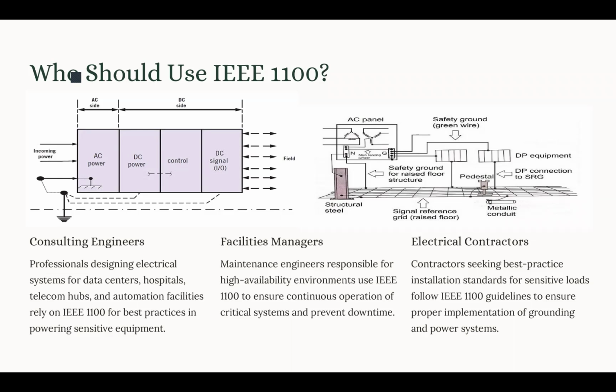Now they have to make sure they have proper grounding and bonding. So basically, bond isolated ground bars directly to the SRGs for sensitive loads, and maintain the neutral to ground bond only at the source transformer, so they can avoid circulating ground current. Another aspect mentioned for the electrical contractor is that they have to use twisted pair or shielded conductors for long distances and long runs, and run the hot, neutral, and ground conductors together in the same conduit, so they reduce inductive noise coupling.